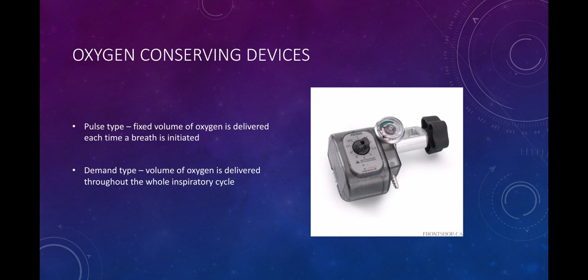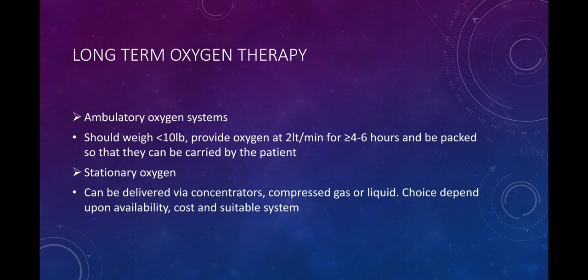Ambulatory oxygen systems should ideally weigh less than 10 pounds, provide oxygen at 2 liters per minute for more than 4 to 6 hours, and be packed so that they can be carried by the patient. Stationary oxygen can be delivered via concentrators, compressed gas, or liquid oxygen. Choice depends upon availability, cost, and suitable systems.